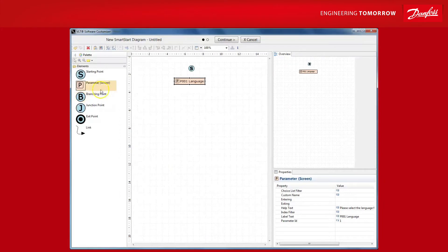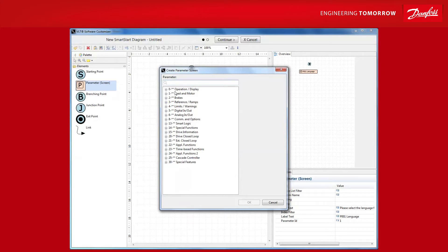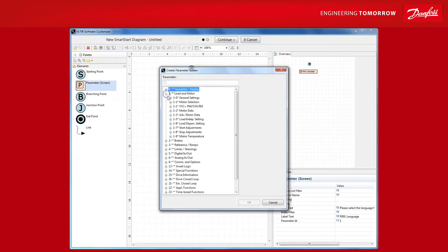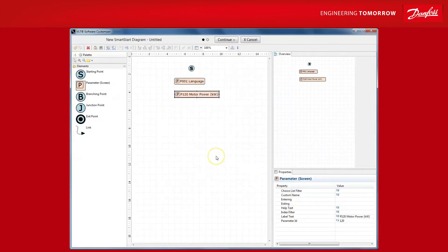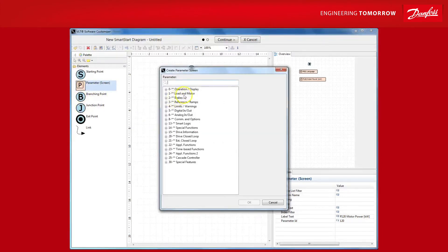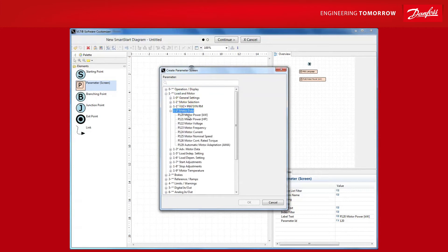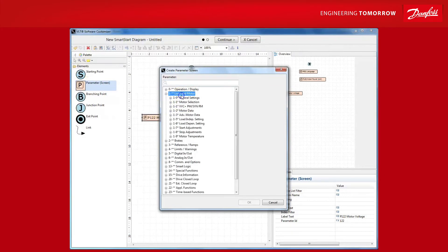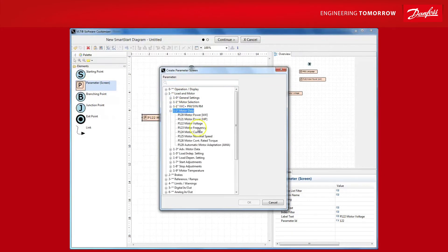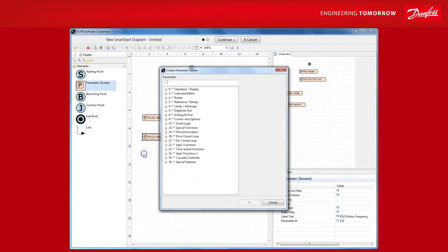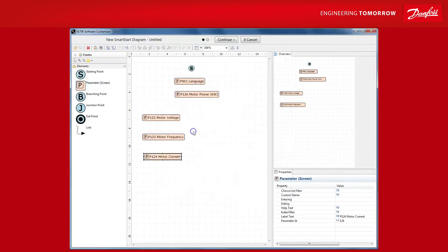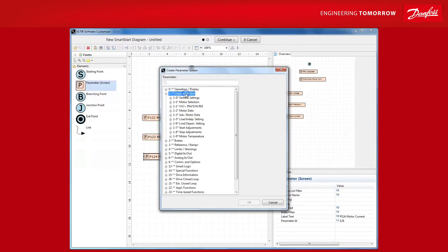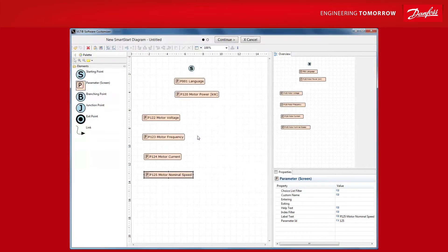Next, we want the wizard to prompt for the motor power. And remember, this is just an example so you can choose whichever parameter or combination of parameters you wish. This time, let's browse for the parameter group. So, one, motor data, motor power, and there we go. Now, let's prompt for common motor data needed for the drive to operate the motor efficiently. Motor voltage, motor frequency, motor current, and finally motor data, motor nominal speed.